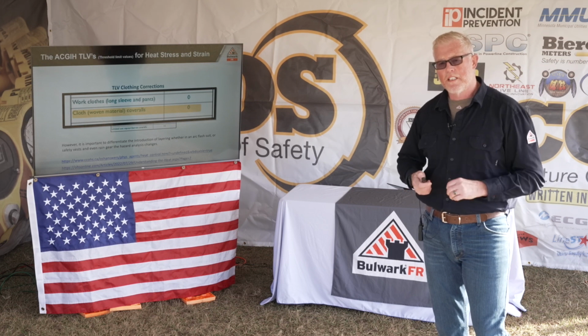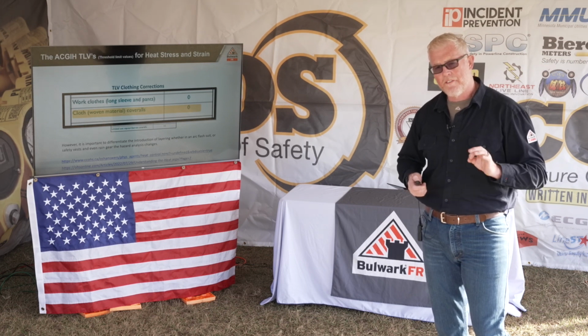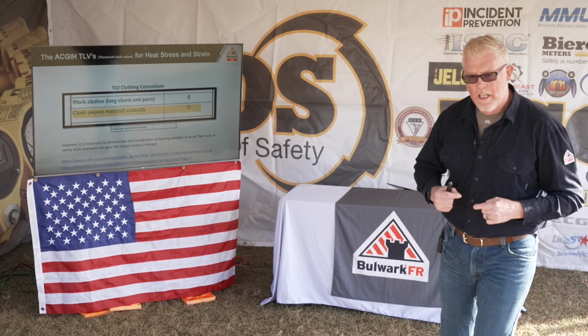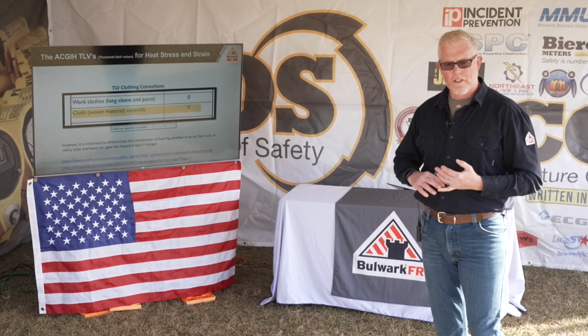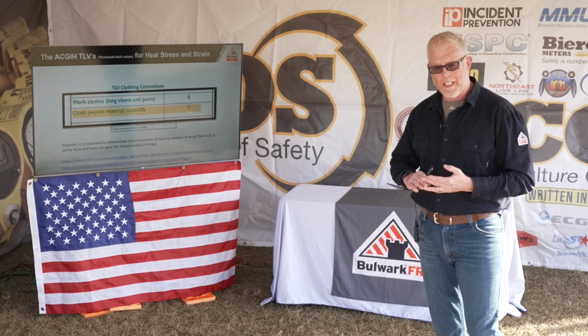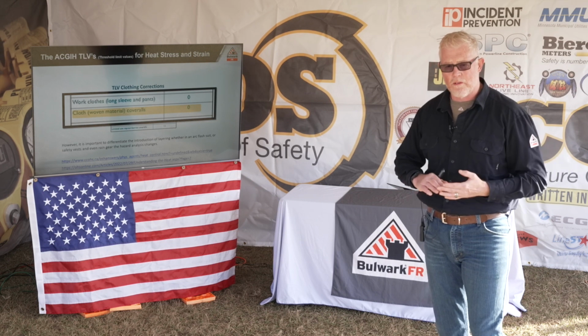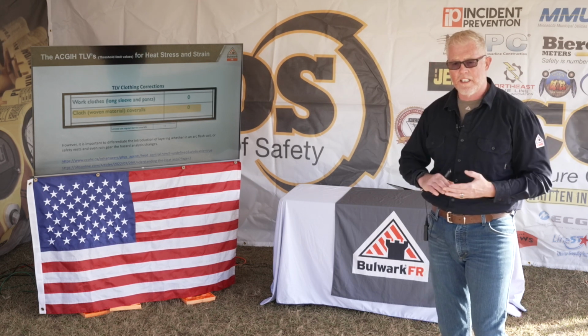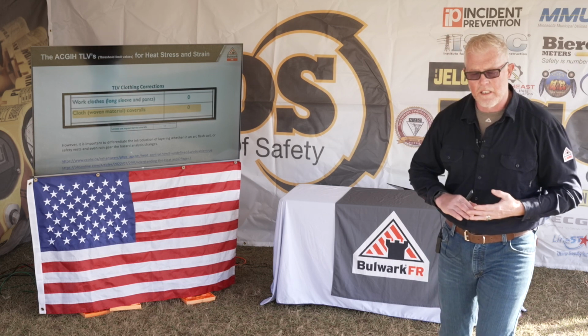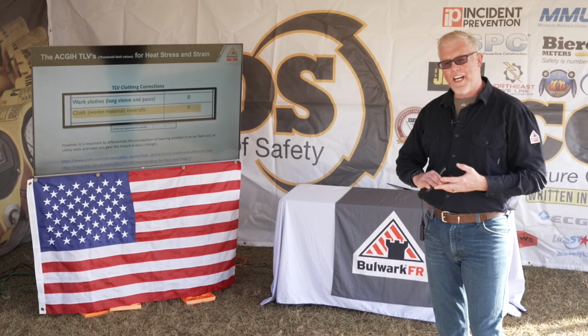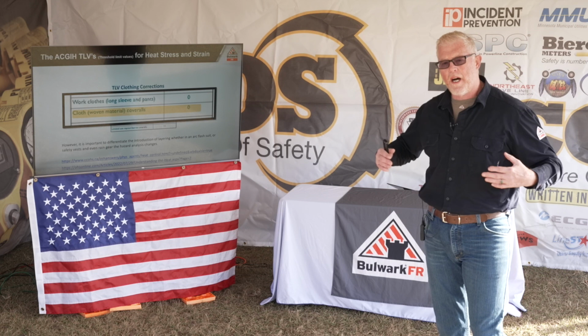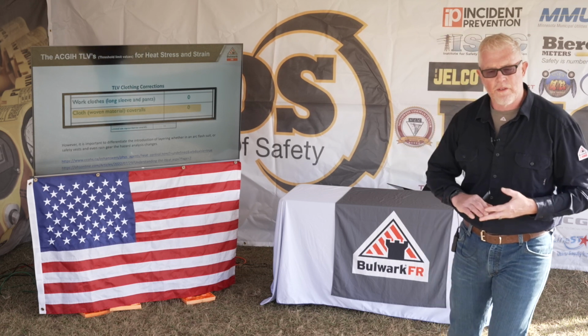Now, that all being said, the caveat is you have to understand that once we go into layering, once you go into arc flash suits, once you go into, for example, inclement weather, you can still have rainstorms when it's 60, 70, 80 degrees outside and now you're putting your rain gear on. Even as simple on a hot day as trapping your body heat by wearing an arc-rated vest.